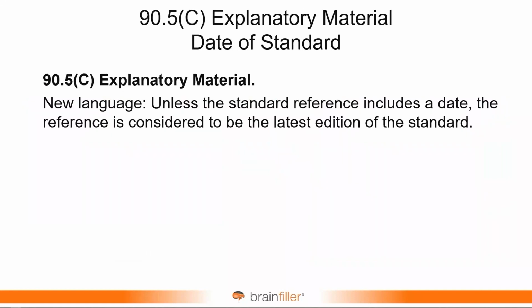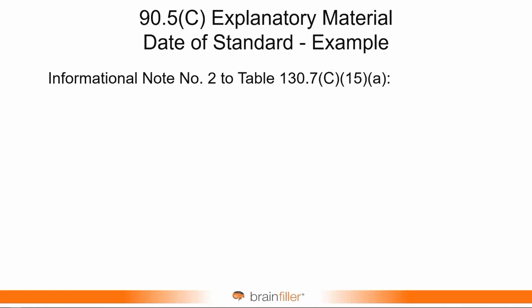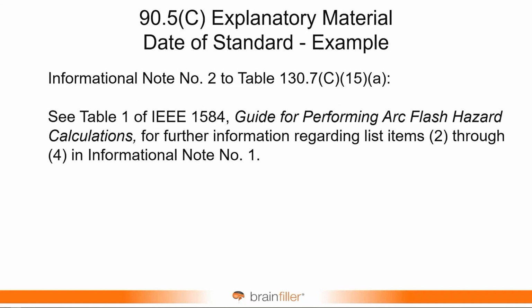The explanatory material, there was new language added here, and it has to do with when other standards are referenced. When you have a standard that's referenced, the question may be, well, is there a date with that reference? So, for example, the PPE category table for AC systems references IEEE 1584 Guide for Performing Arc Flash Hazard Calculations, except it doesn't tell you which date, which edition to use. And this is fairly common.